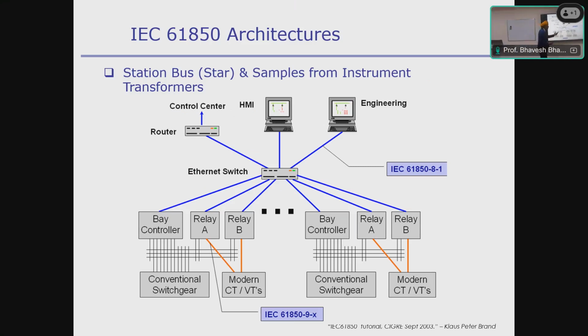And that's why sometimes you divide the process bus also, because you only need that type of data from those devices. So you divide them. Again, it's up to you, it's very flexible. This is why I say they are all unique in a similar way, following IEC 61850, but unique. You can have any unique combination. And setting up this doesn't take very long. With that tool, you can set up the whole substation in a few hours, compared to what they do now with hardwired connections and so on.